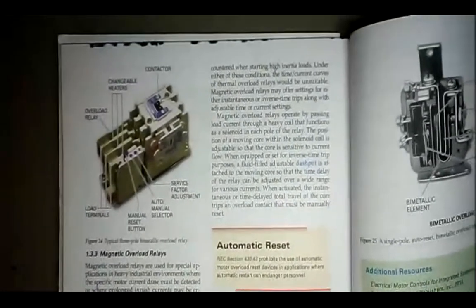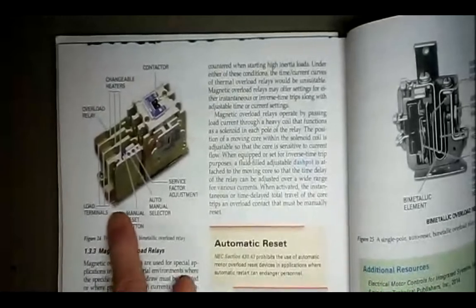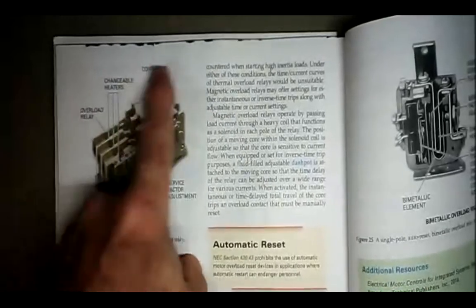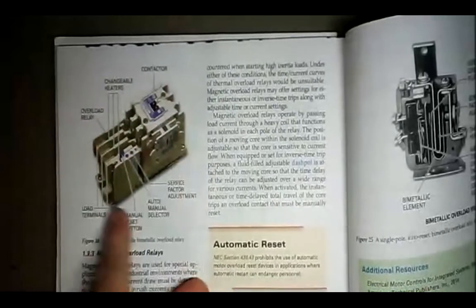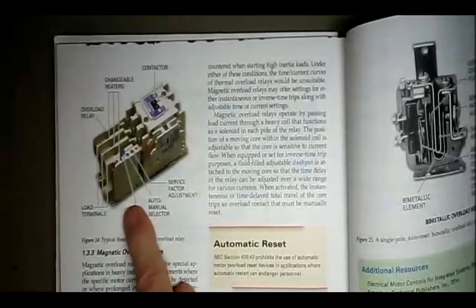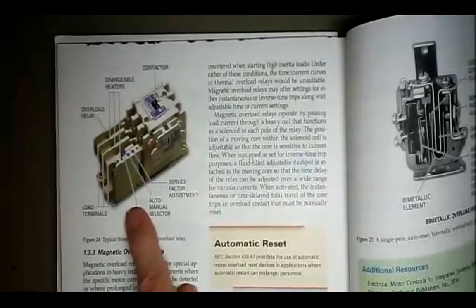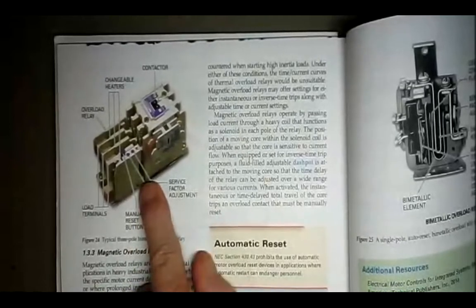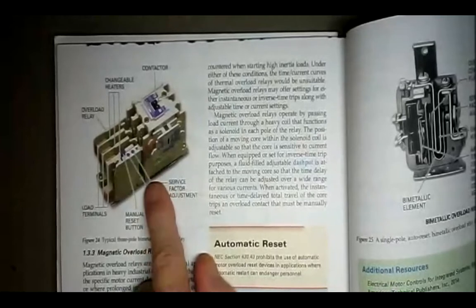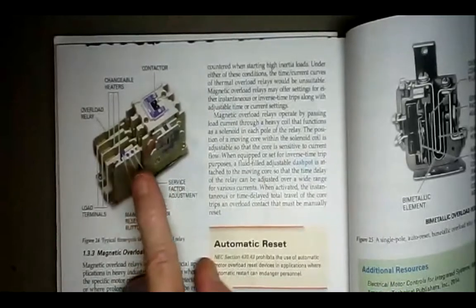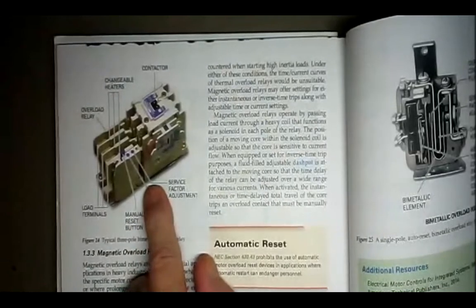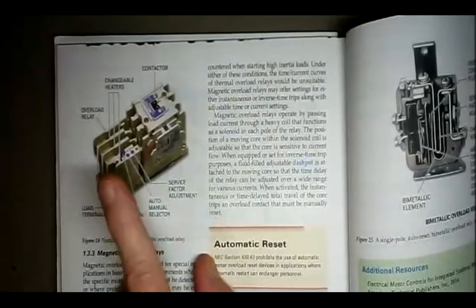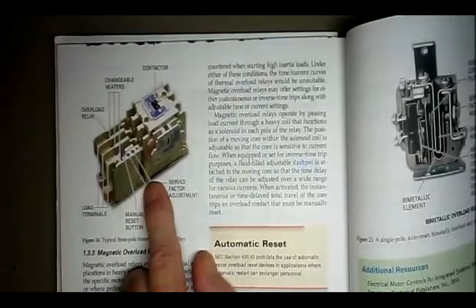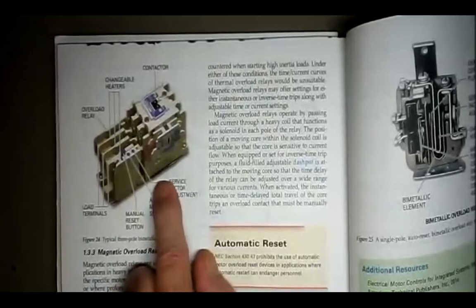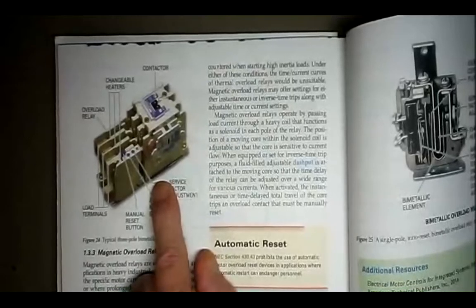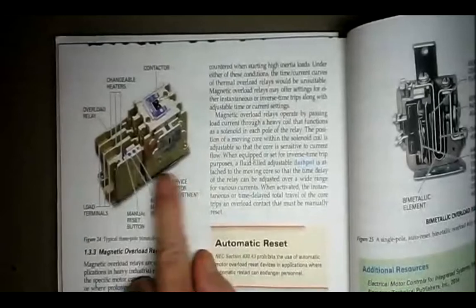This is an example of an IEC, International Electrotechnical Council, Technical Council. This is an IEC rated one. It's my understanding that the IEC contactors, motor starters, are smaller, they're lighter, they're cheaper, but they only work about half as long. You'll get 2 million operations out of a NEMA starter. You'll get about 1 million operations out of this IEC starter. But people are going to these IEC frames because they are economically feasible and they're very easy to change out.